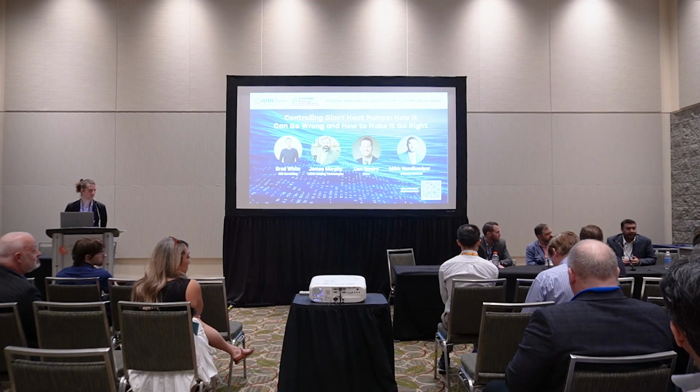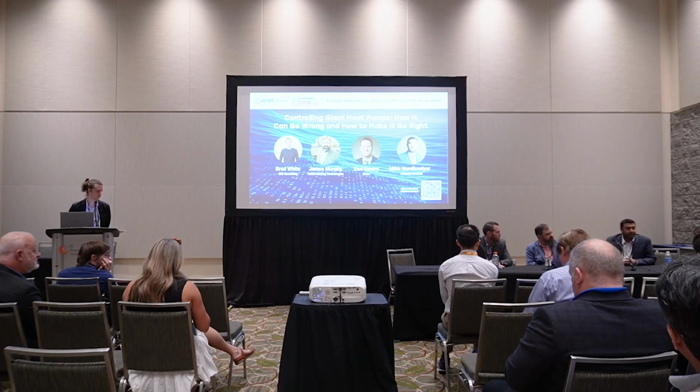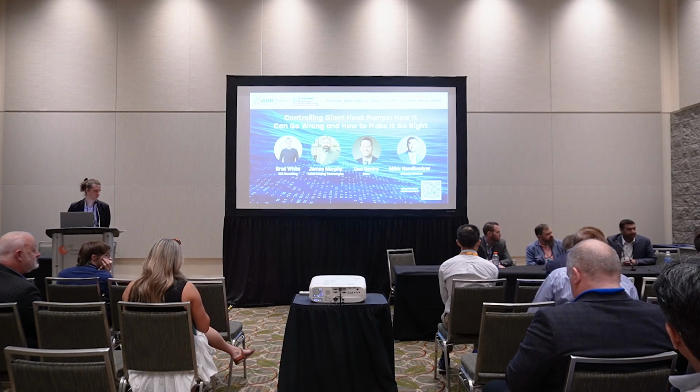A couple reasons why we may not just want to run for a number of minutes is if you're at such a low load and I'm beyond my max outlet temperature and I'm at a pressure limit or a freeze protection limit, if I'm water sourcing, it's better not only for the safety of the equipment. If you're looking at hitting a pressure limit and bursting something, the safety would probably hit before you even got to that point. On the refrigerant side, right?